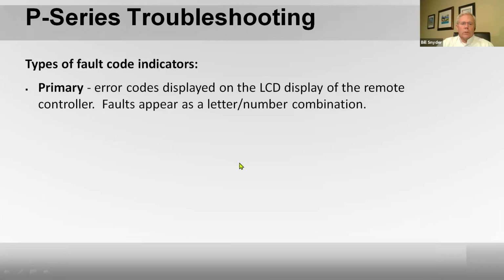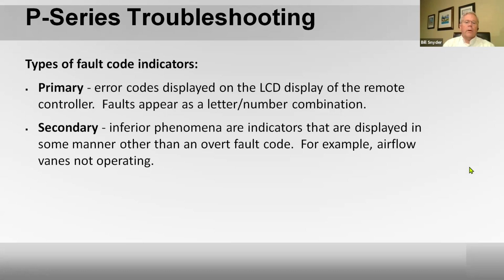In the instructions, occasionally there are primary codes which are displayed on the LCD of the remote controller, the thermostat. The faults appear as a letter-number combination, as I mentioned. Secondary, it would tell you it's an inferior phenomenon. Those are indicators that are displayed in some other manner other than a fault code. It may not be a flashing light. It may not be the alphanumerical two-character code on the remote controller. An inferior phenomenon is something that it's not picking up on.